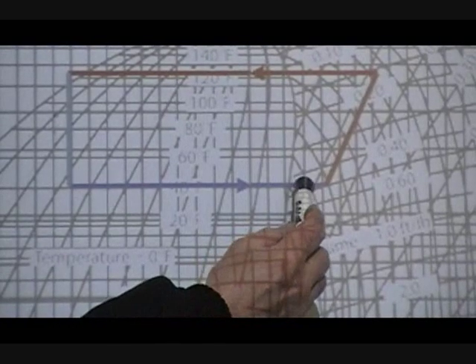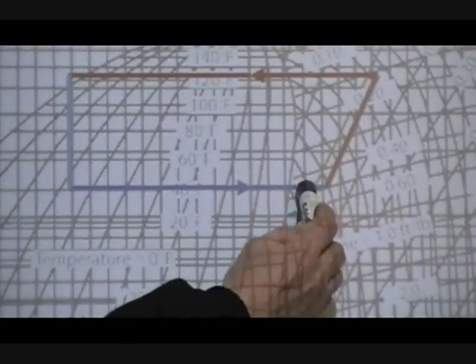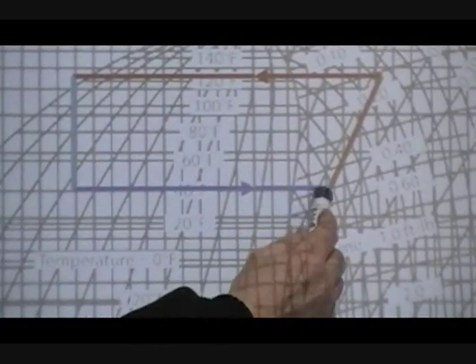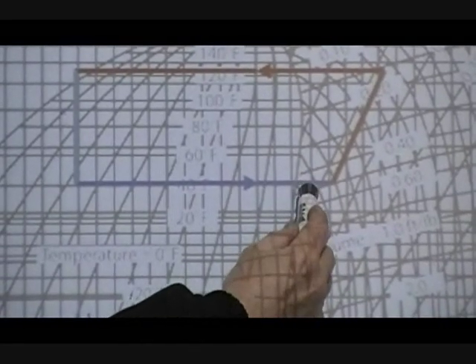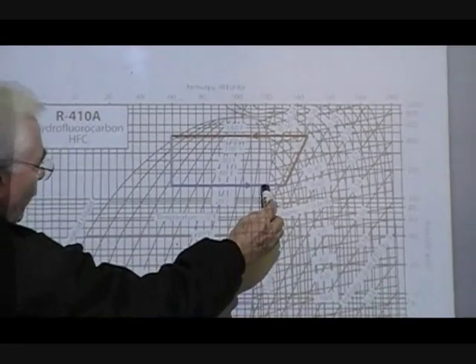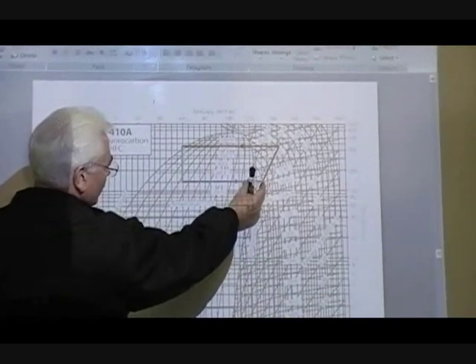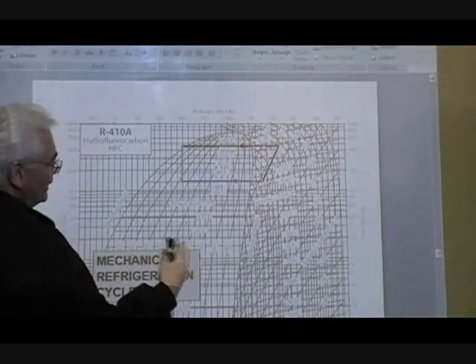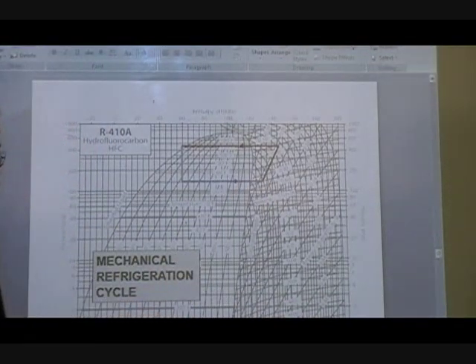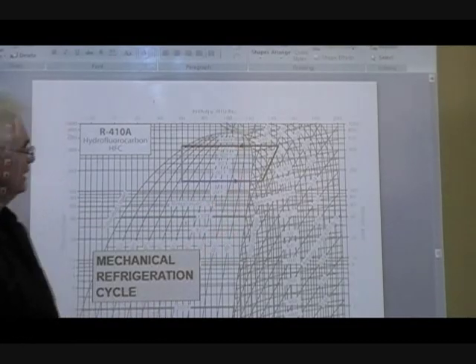But this is where the real work is done. And if you'll notice, if you start here at 60 and come over here to the point where all your liquid boils off, it's 100% vapor. And that's going to occur on this 100% saturated vapor curve. At that point, this little bit here is where you're going to pick up superheat. What's the definition of superheat? Any heat that's absorbed into the vapor beyond the point of saturation.